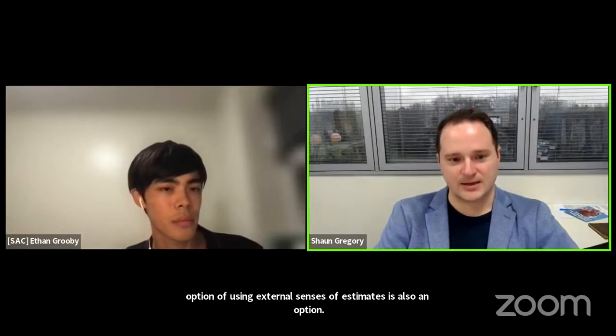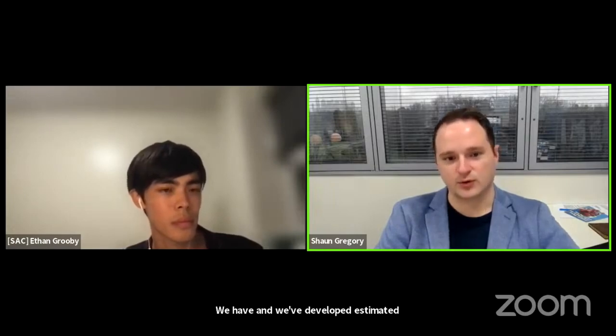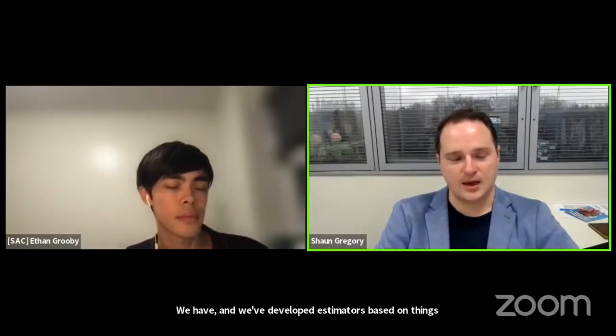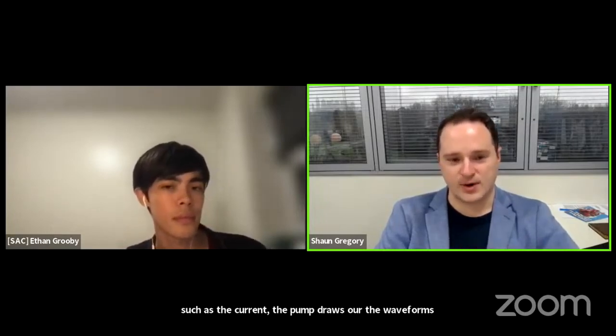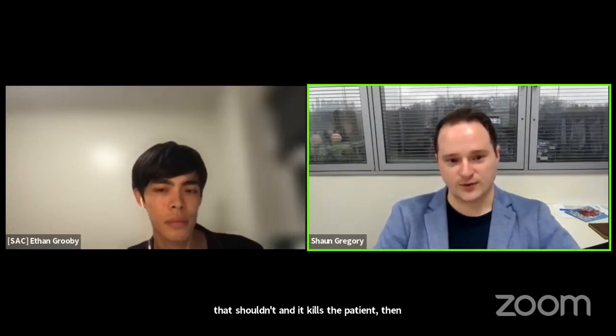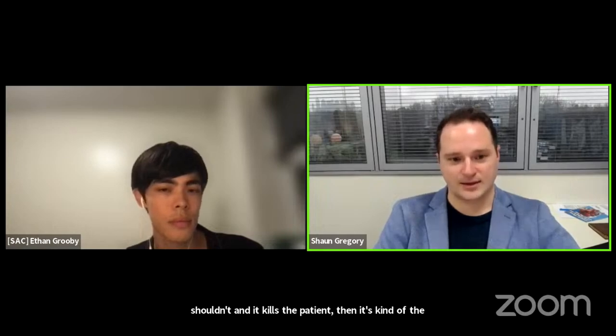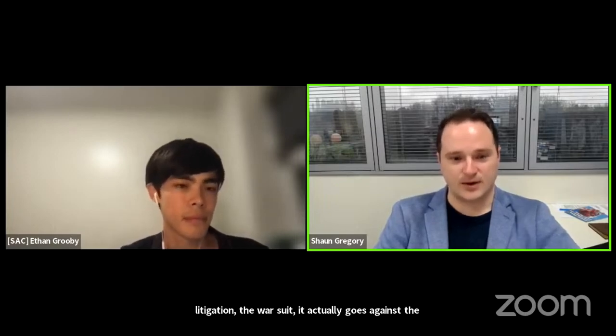We've developed estimators based on things such as the current that the pump draws, the power, the waveforms that we see in the pumps, things like that, that give us an estimation of what those pressures might be. But those estimations are not perfect. And if you think about it, if the estimation gets it wrong and the device does something that it really shouldn't and it kills the patient, then it's kind of the fault of the manufacturer. And in that case, the litigation, or the lawsuit, potentially goes against the manufacturer, which is obviously a really big risk for the manufacturer to adopt that.